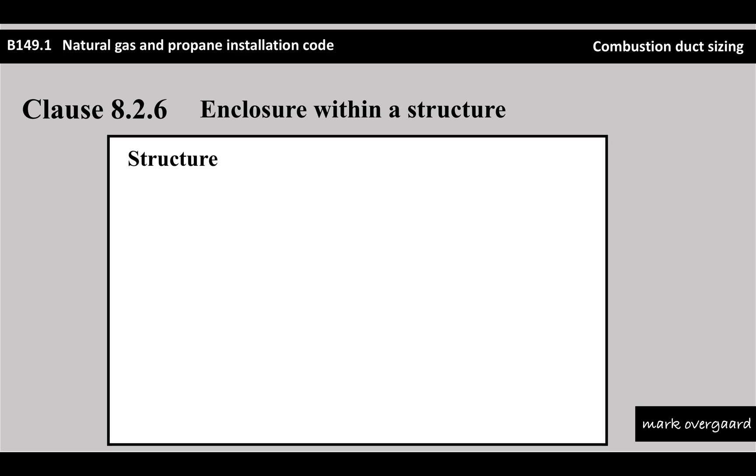So we're starting with a structure - think of something like a warehouse. This particular clause only works with this scenario: we have to have a low-volume installation, meaning the combined inputs of all the appliances within the enclosure have to be less than 400,000 BTUs.